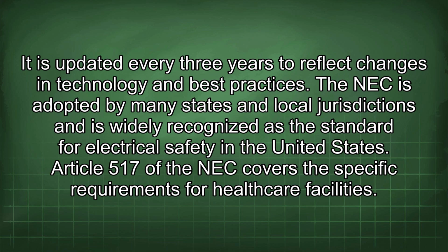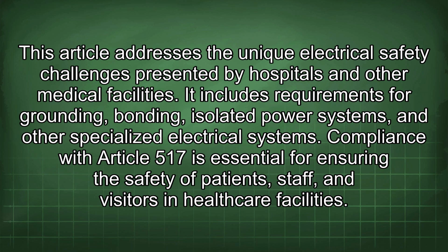The NEC is adopted by many states and local jurisdictions and is widely recognized as the standard for electrical safety in the United States. Article 517 of the NEC covers the specific requirements for healthcare facilities. This article addresses the unique electrical safety challenges presented by hospitals and other medical facilities. It includes requirements for grounding, bonding, isolated power systems, and other specialized electrical systems. Compliance with Article 517 is essential for ensuring the safety of patients, staff, and visitors in healthcare facilities.